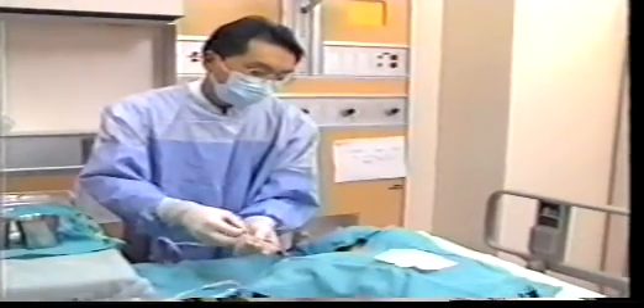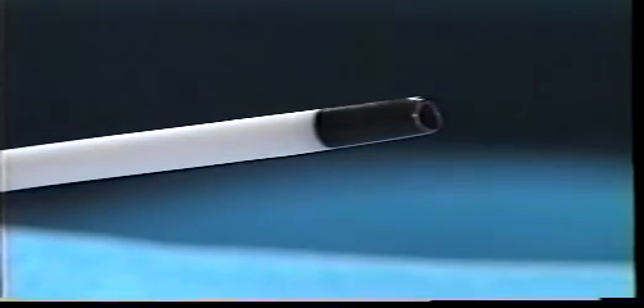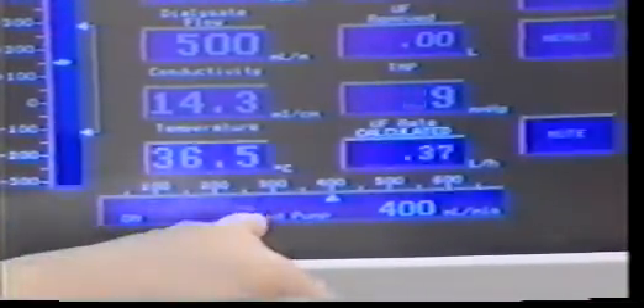And again, excellent flows. The Niagara PC catheter is designed with a beveled arterial lumen to facilitate insertion. The blunt venous tip reduces pressure at a set blood flow rate. The round lumens allow blood flow rates up to 400 milliliters per minute at a venous pressure of less than 250 millimeters of mercury, as suggested by in vitro data.